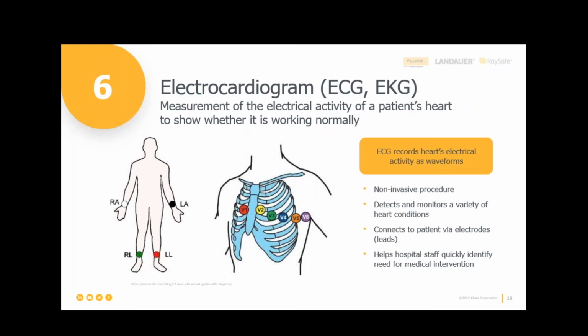So the measurement that we need to make, not just on the monitor screen, but on the strip chart paper as well, is number one, make sure the strip chart paper is spooling at the rate that we think it is. You need a marker and a stopwatch to do that. You don't need anything more than that. Make sure that that's working. Then the next thing you want to do is make sure that when you push the button for a 1 millivolt cal pulse, on the strip chart paper you see 1 millivolt in amplitude. And it's that 1 millivolt in amplitude that is actually, besides heart rate, the metrological measurement we're looking for. Because anything about the arrhythmia, the rhythm of the heart, the dysrhythmia of the EKG signal, is not something we can assess electronically.